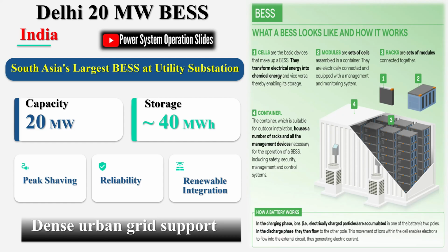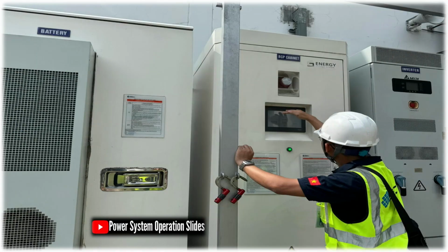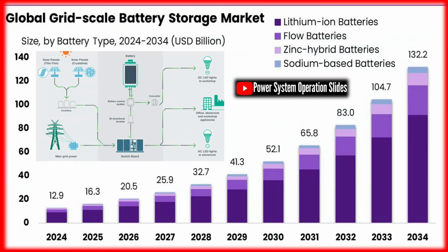This finding challenges the common assumption that lithium-ion battery cells constitute the primary source of failures. Instead, the balance of system, BOS, and controls systems account for the vast majority of failed components, with cells representing only 11% of classified incidents. The BOS encompasses a wide range of components including DC and AC wiring, HVAC subsystems, safety elements such as fire suppression systems, enclosures, power conversion systems, transformers, and thermal management systems.